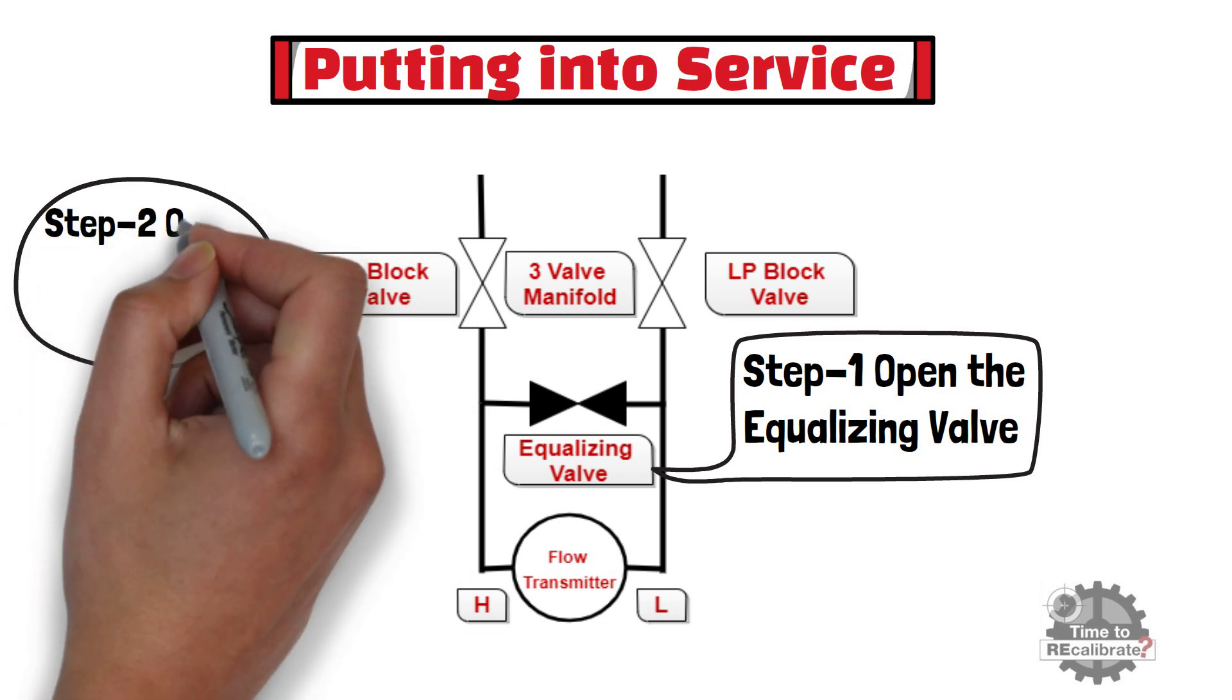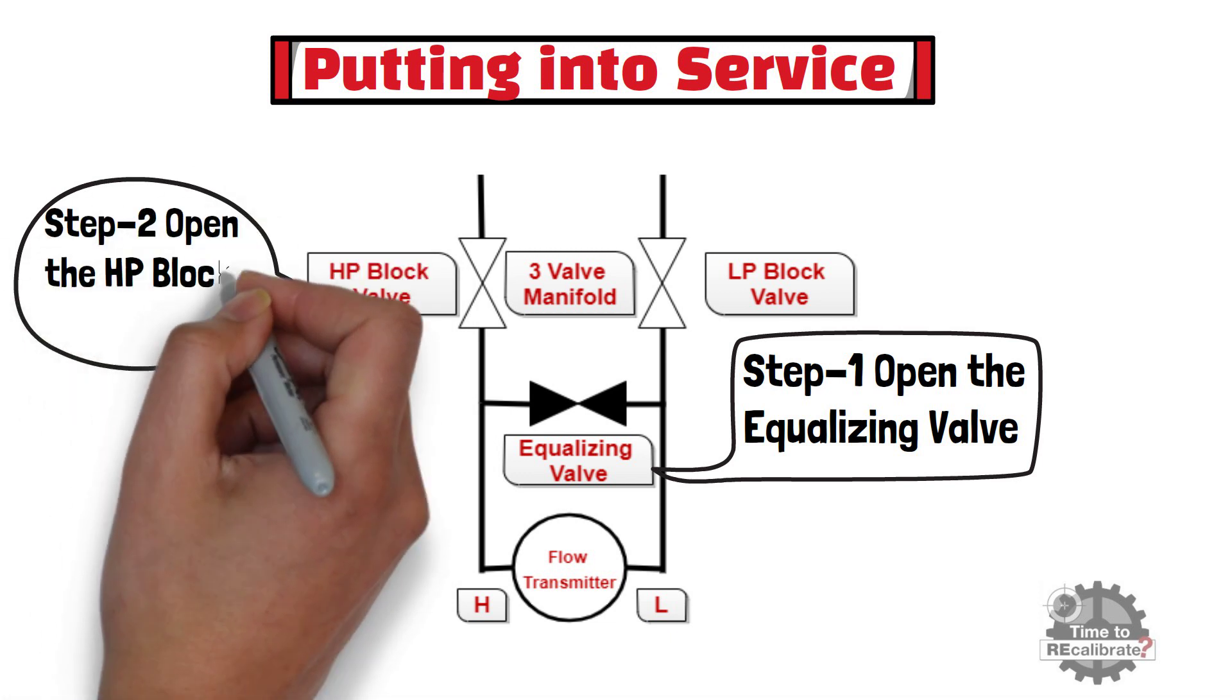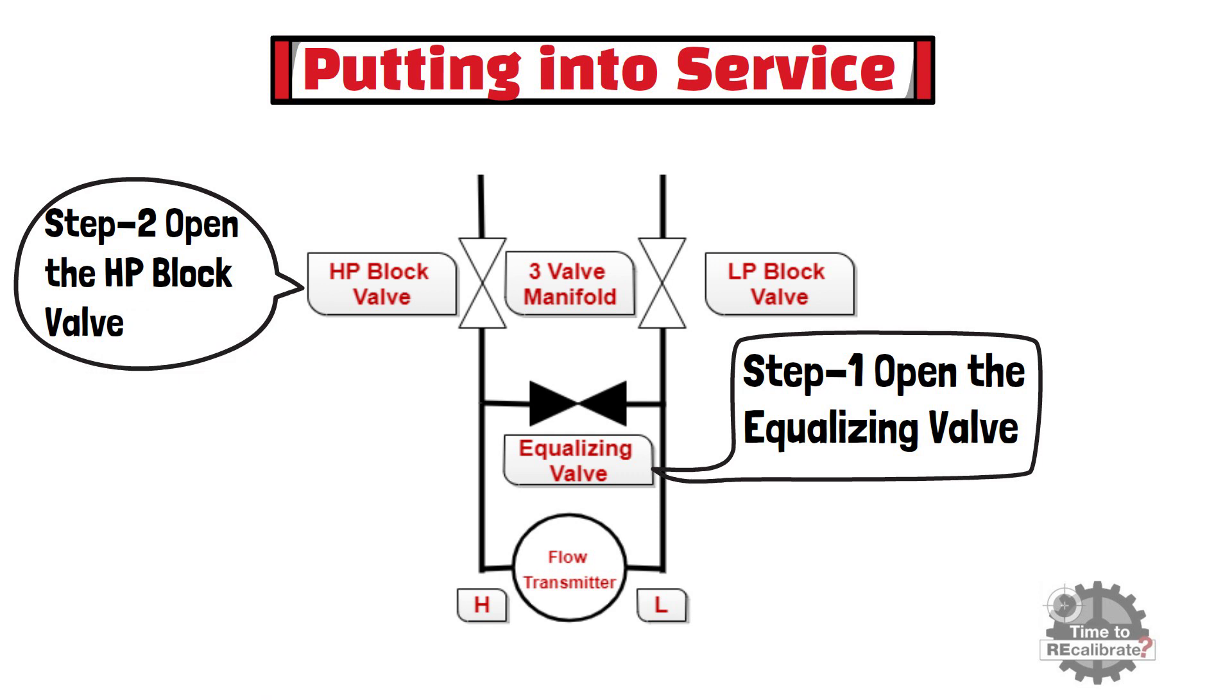In step 2, open the HP block valve by rotating valve in counterclockwise direction. Once we open HP block valve, both sides of the transmitter will be at the same pressure, which is equal to the HP side of the process pressure.